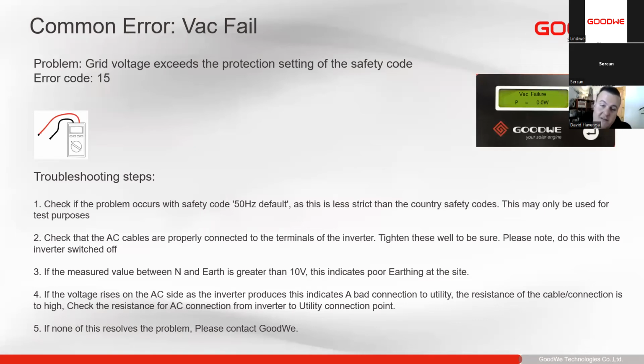What I always like to say is, if you have a screen or you connect it via the SolarGo app, you can have a look at what the grid voltage is. If you see the grid voltage is quite high, we restart the system, let it start back up again. When the inverter is off, or not producing, we can see what the grid voltage is. If the grid voltage is within range, we start the inverter up. If we see that voltage immediately start to climb, then you can be sure there is a resistance issue.